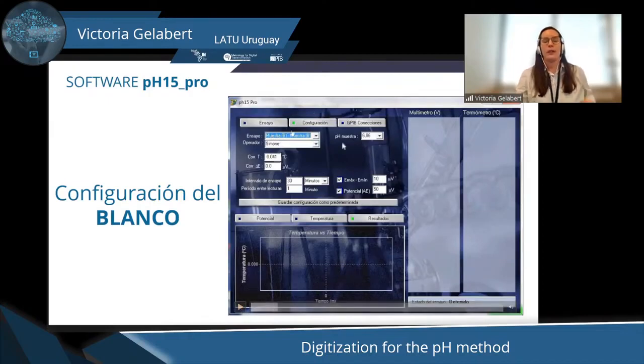First of all, it's going to give you that information. So this is sample to sample. Why sample to sample? Because first of all, I'm going to include in both compartments the same sample. So I'm going to turn everything off. I'm going to put it back on. In order to see whether there might be a slight difference between both compartments, or a difference in the electrode disposition between both electrodes, or it could be that both compartments might not be exactly the same in terms of behavior. I'm going to want to reflect that in the final results.